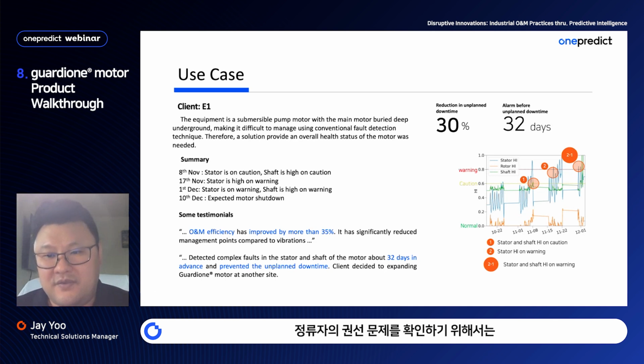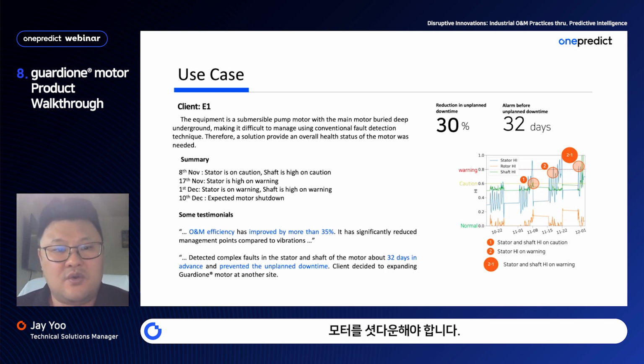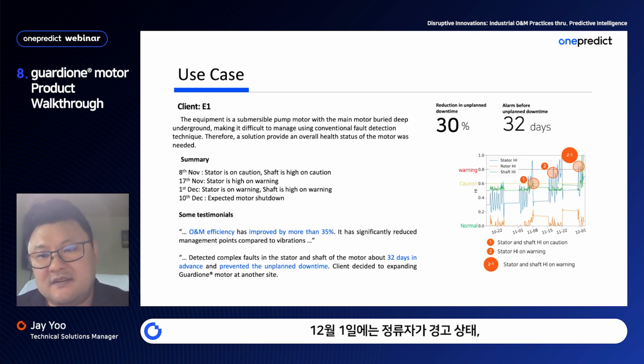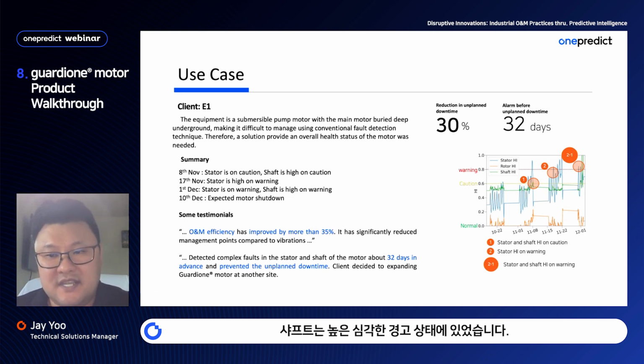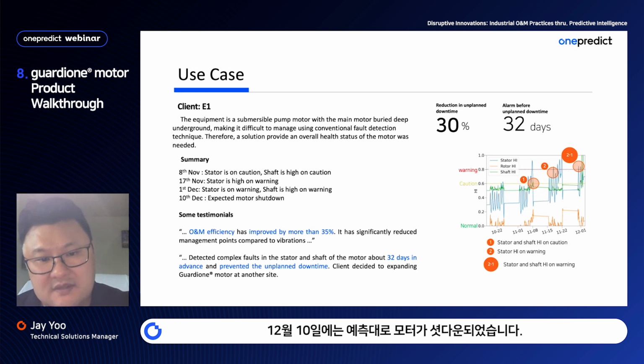To confirm it's just a stator winding issue, the motor would have to be shut down, which for a critical asset like this isn't possible, as it would jeopardize operation. On November 17th, stator is high on warning. On December 1st, stator is on warning and shaft is high on warning. On December 10th, the motor shut down as expected.